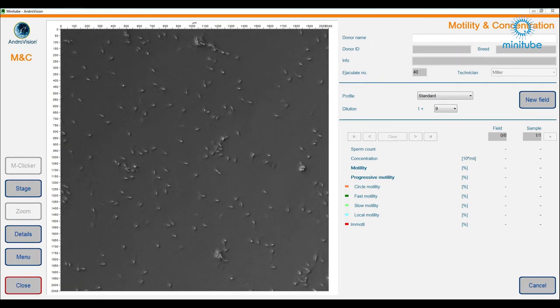This is how the sperm cells look like if the phase contrast is not adjusted properly. The cells don't look as bright as normally and everything appears grayish. Please readjust the phase contrast correctly.